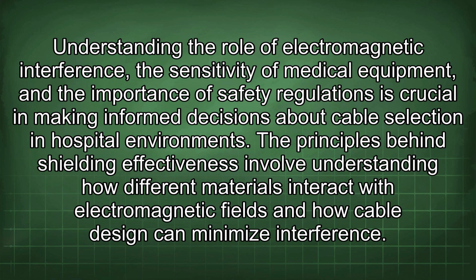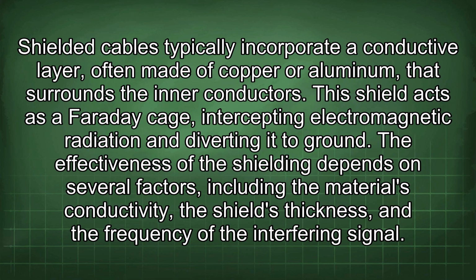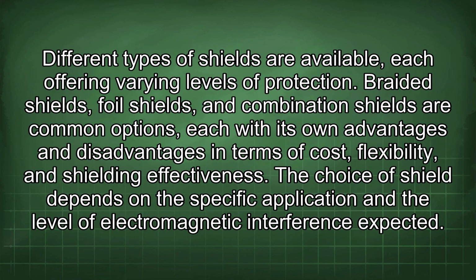The principles behind shielding effectiveness involve understanding how different materials interact with electromagnetic fields and how cable design can minimize interference. Shielded cables typically incorporate a conductive layer, often made of copper or aluminum, that surrounds the inner conductors. This shield acts as a Faraday cage, intercepting electromagnetic radiation and diverting it to ground. The effectiveness of the shielding depends on several factors, including the material's conductivity, the shield's thickness, and the frequency of the interfering signal. Different types of shields are available, each offering varying levels of protection. Braided shields, foil shields, and combination shields are common options, each with its own advantages and disadvantages in terms of cost, flexibility, and shielding effectiveness. The choice of shield depends on the specific application and the level of electromagnetic interference expected.